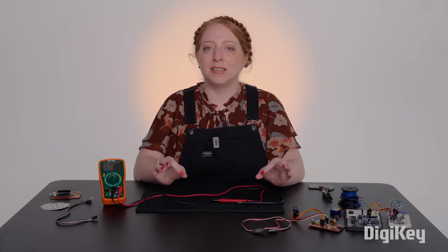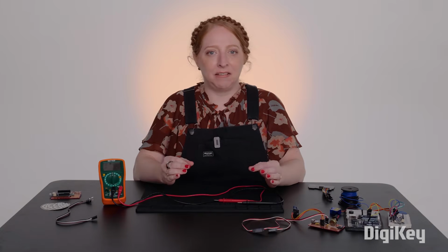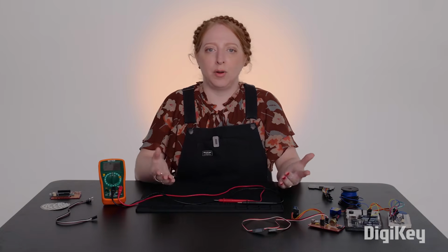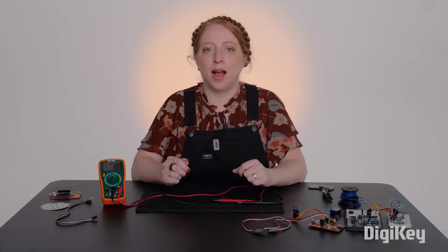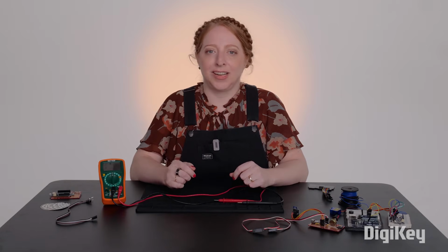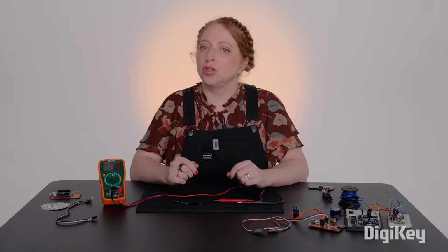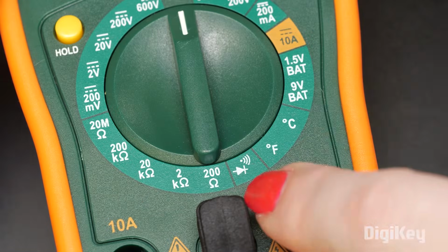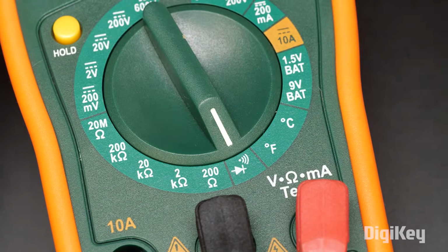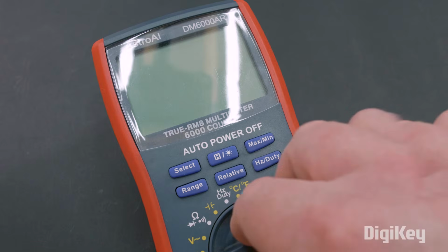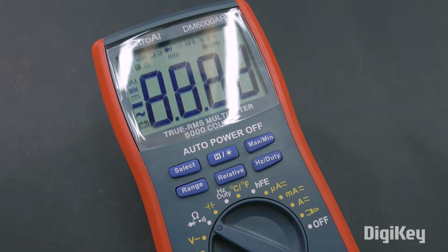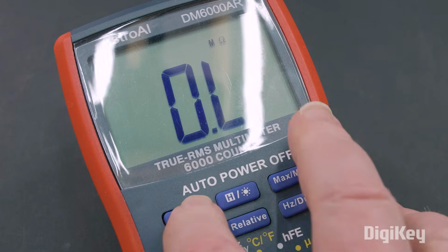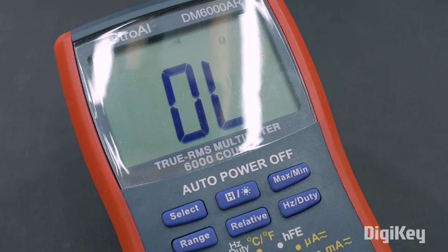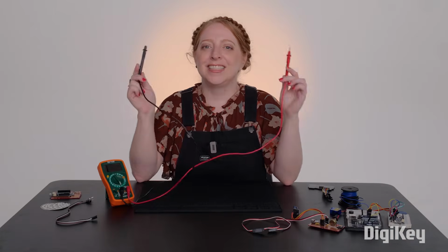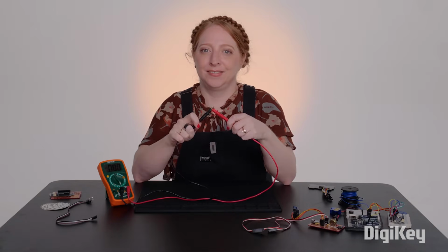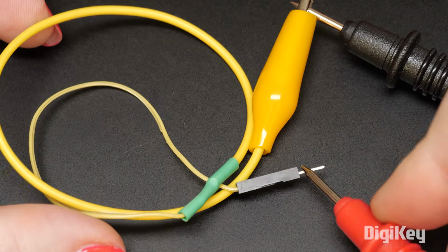First up is a simple continuity test. This just checks if electrical current is able to flow between the two probes and can help spot a bad solder joint as well as short circuits. For this test, the circuit power should be off. Turn the dial to the speaker icon. Some multimeters have multiple functions on this setting, so you may also have to press a mode button until the speaker icon appears. To check that you are successfully set to continuity testing mode, touch the probes together. The meter should beep to indicate continuity.